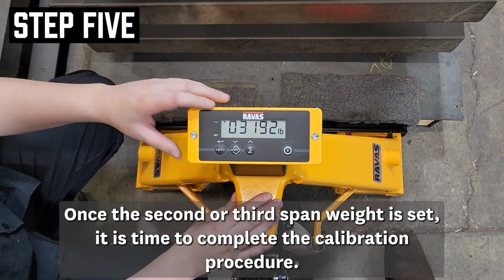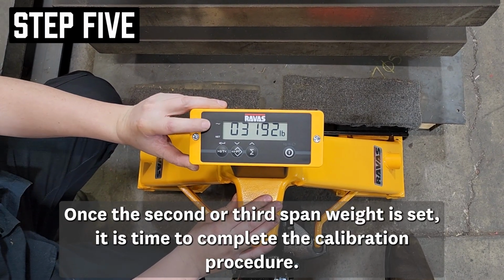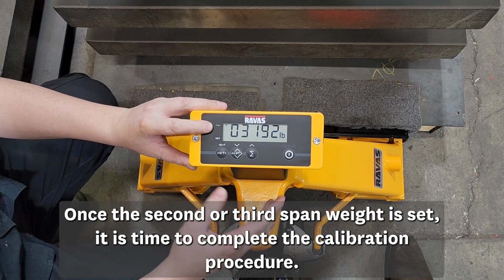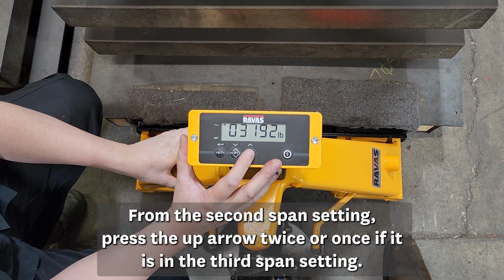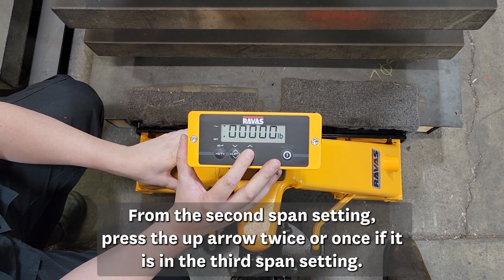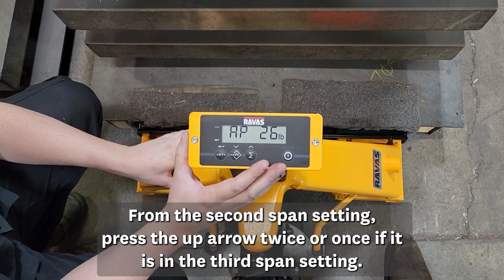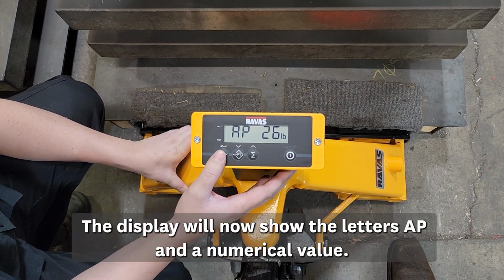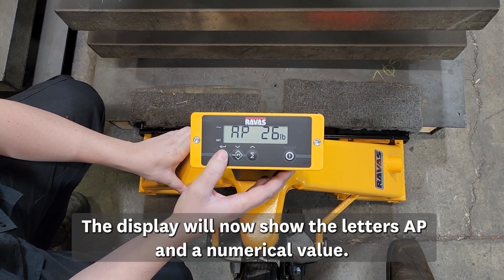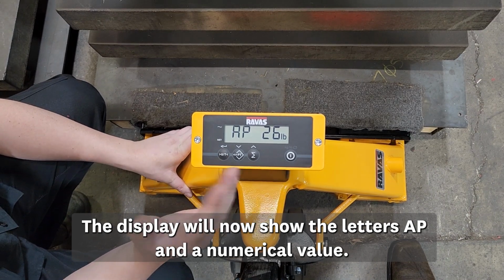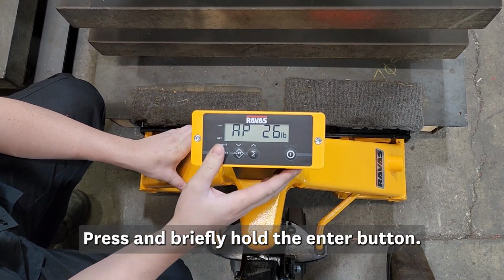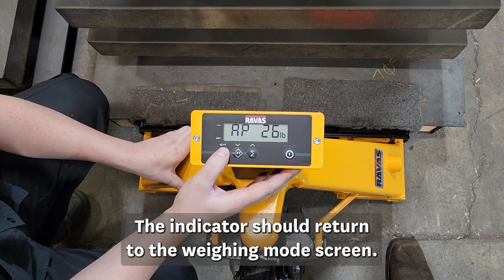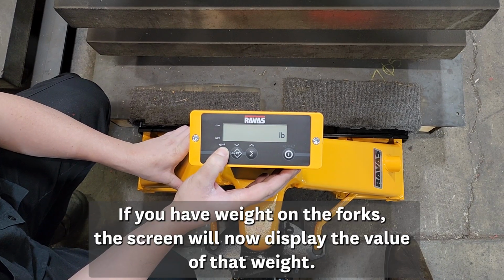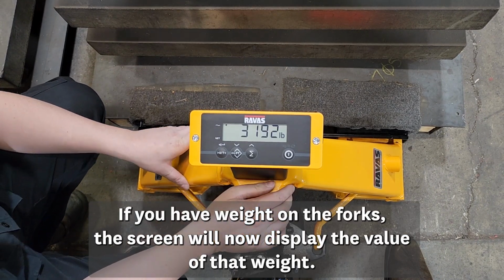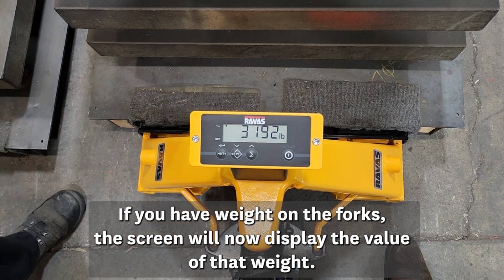Step 5. Once the second or third span weight is set, it is time to complete the calibration procedure. From the second span setting, press the up arrow twice, or once if it is in the third span setting. The display will now show the letters AP and a numerical value. Press and briefly hold the Enter button. The indicator should return to the weighing mode screen. If you have weight on the forks, the screen will now display the value of that weight.